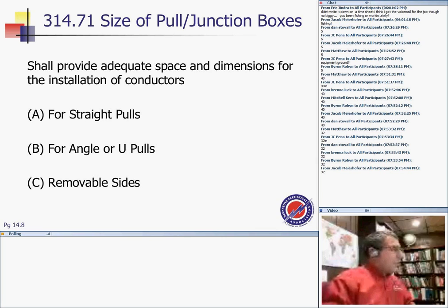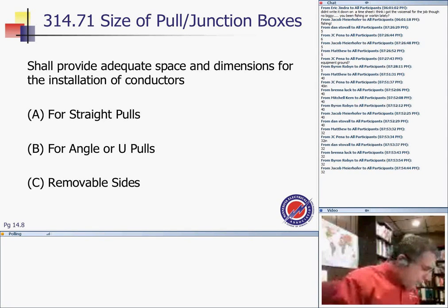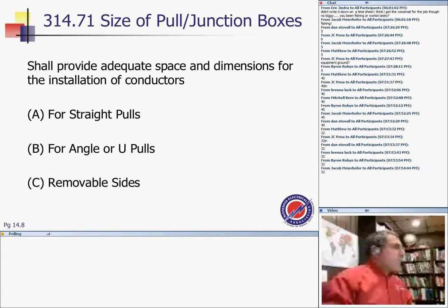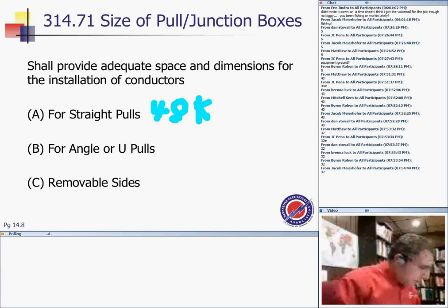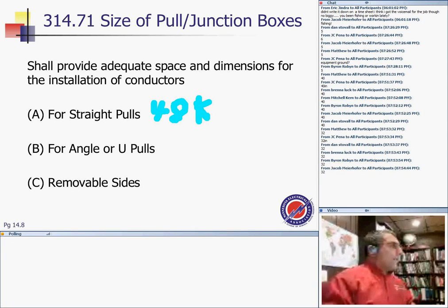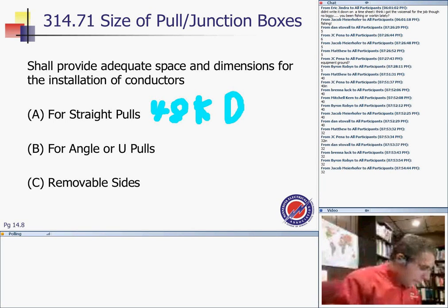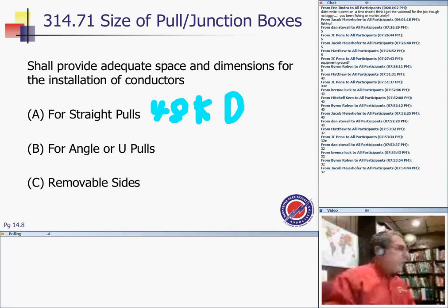Interesting. The pull boxes for higher than 600 volts, believe it or not. Number one, the sizes of pull boxes, terminals, pull boxes, and so forth. For a straight pull, and you probably have never seen that one, it is 48 times the outside diameter or sheath of the largest shielded or lead-covered conductor or cable entering the box. The length should not be less than 32 times the outside diameter of the largest non-shielded conductor. So if it's shielded, it's 48; if it's non-shielded, you go 32 times.